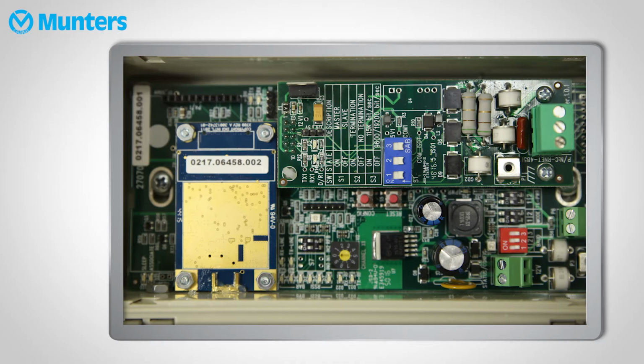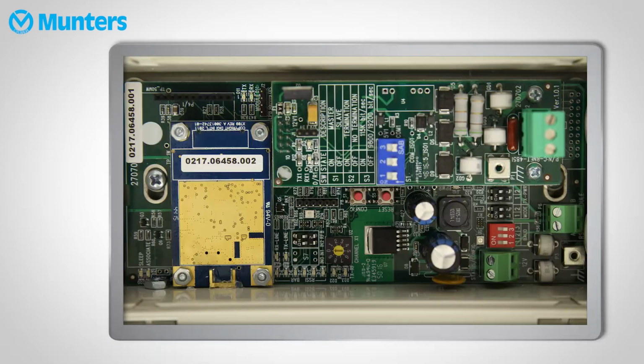One other thing to check is inside the R-Link 1. There is a potentiometer which defines the channel. This was designed to avoid mixed signals between closed farms. Double check and make sure your channels are the same throughout the farm. After that, check mode, power level, and communication protocol dip switches. All these are detailed in the R-Link 1 video and manual.